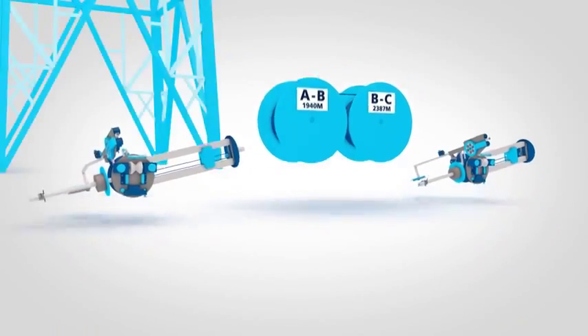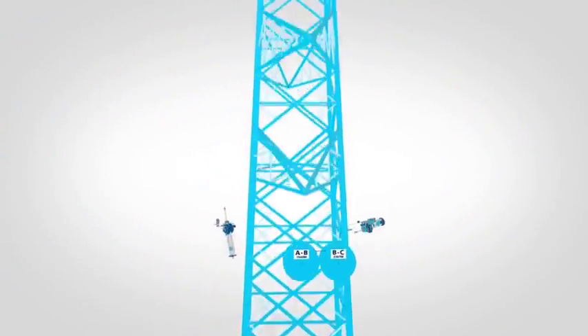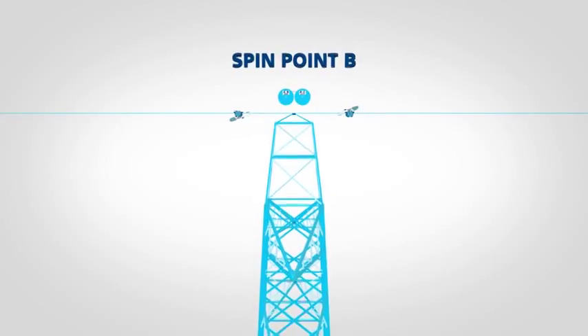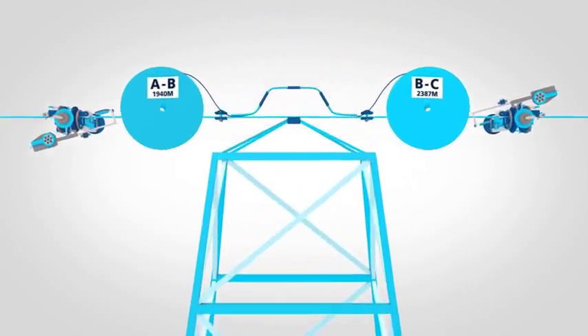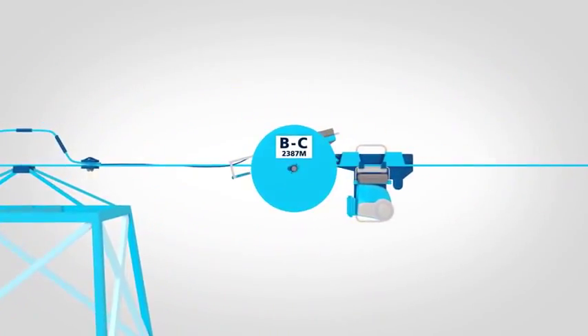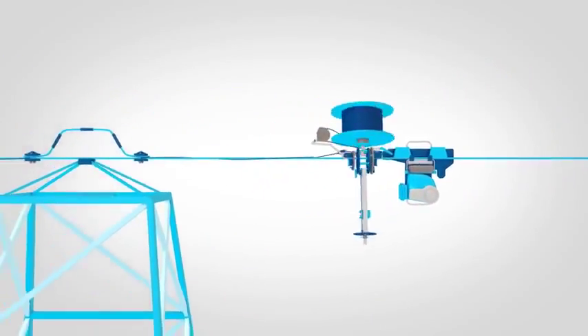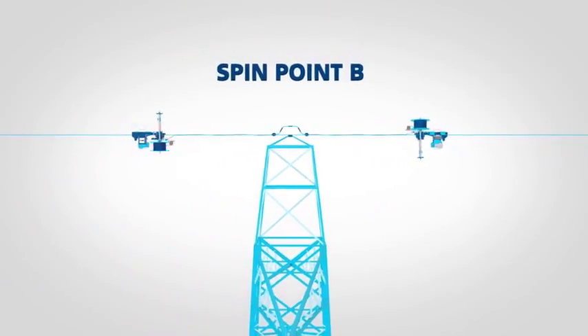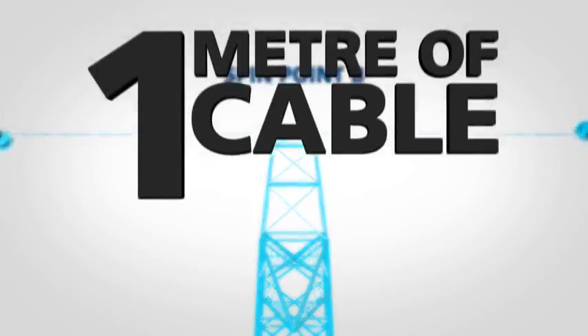Installation begins by hoisting wrapping machines and a cassette onto the line at a starting location or spin point. The cable joining the two drums is secured to the host conductor and then the wrapping machines begin their work. Radio controlled tugs pull the machines away from the spin point over the conductor in opposing directions. Each machine is capable of wrapping up to one meter of cable per second.